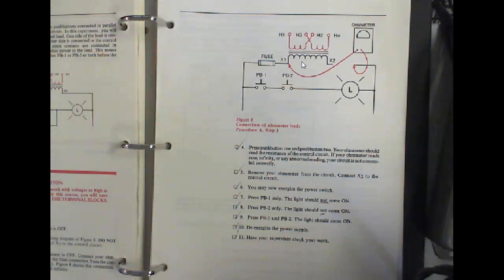But what we want to do is check for short circuits, and the best way is to use your ohm meter. So we're going to disconnect one of the wires. Why disconnect one of the wires? Because if you put it between L1 and L2 with power off, we want to make sure power's off, of course I'm controlling that. You don't ever want to put it on there to equalize.